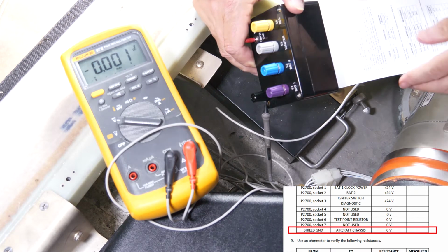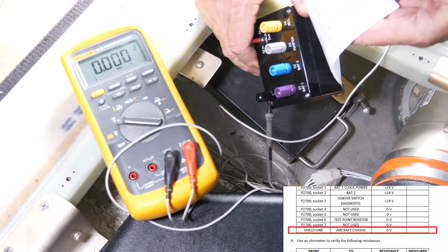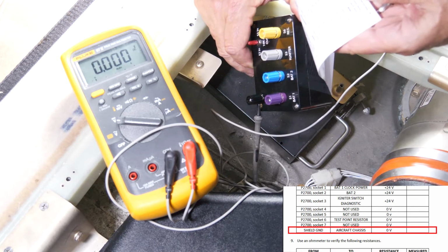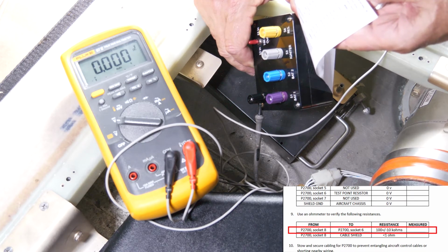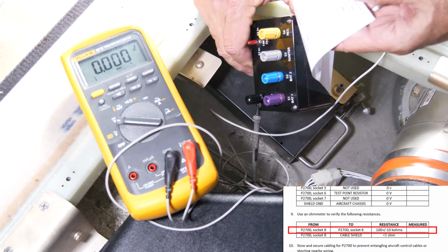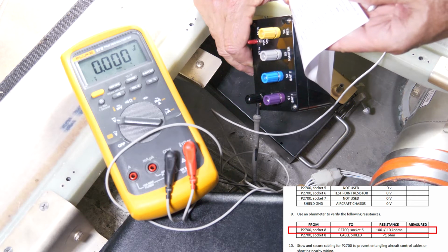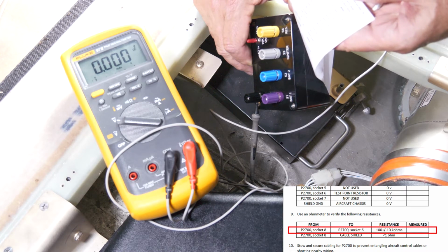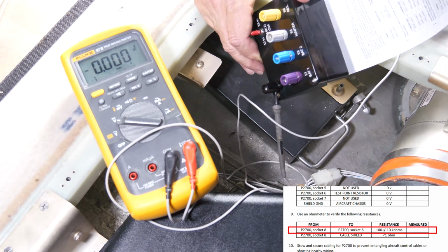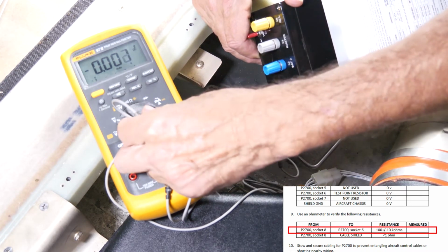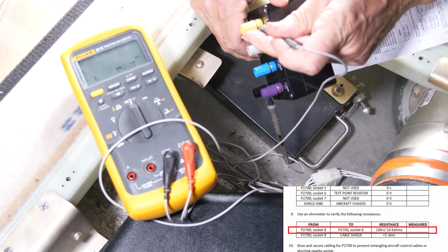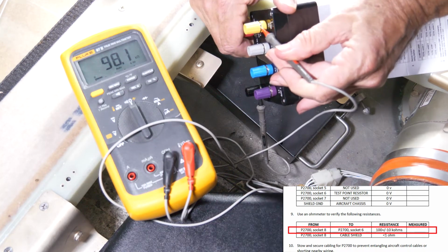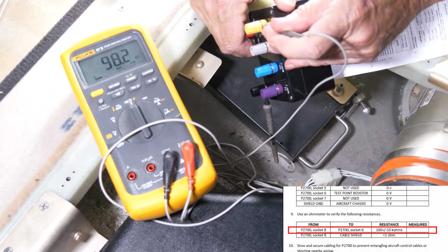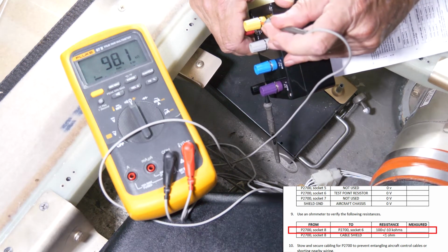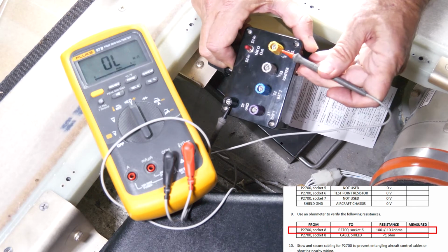So the last test here, there are two resistance tests. The resistance between socket 8 and socket 6 is supposed to be 100 k ohms plus or minus 10 k ohms, I guess. So socket 8 and 6, switch this to ohms, and we've got 98 k ohms. So that passes.